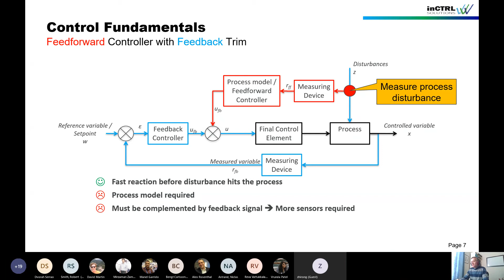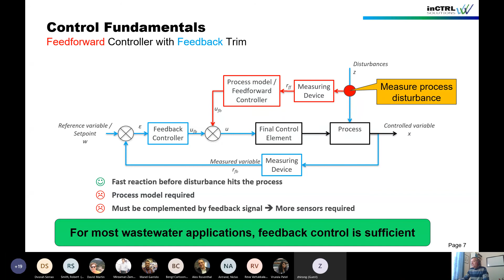So I'd say you should always have a feedback signal attached to it. In my experience, for most wastewater applications, feedback control is sufficient. Clearly check if you really need feed-forward control—if feedback alone works, that's the much more robust solution, and I'd recommend keeping it simple.